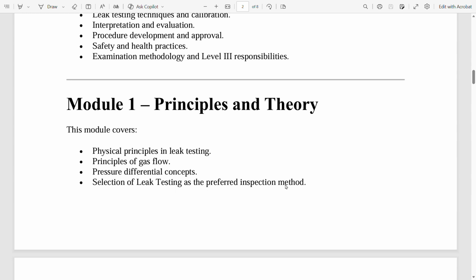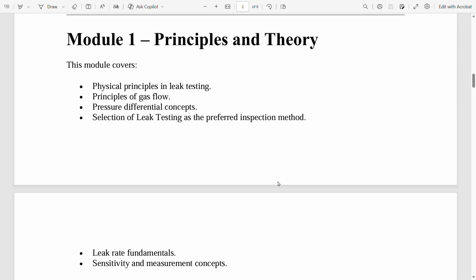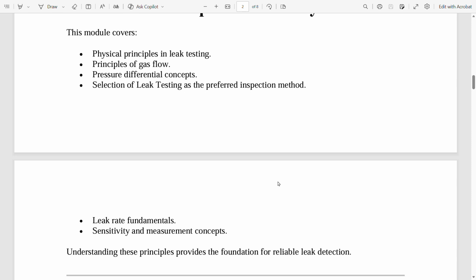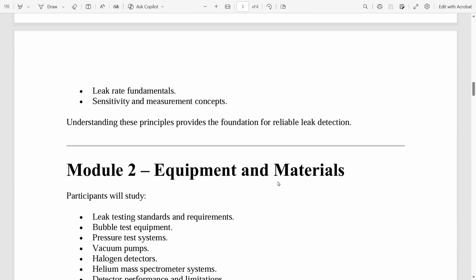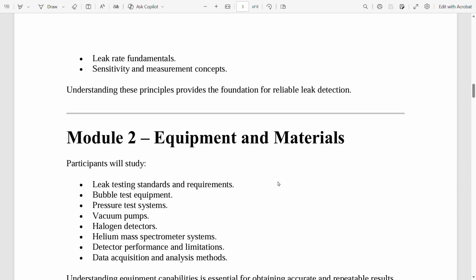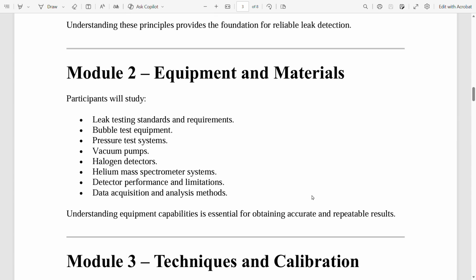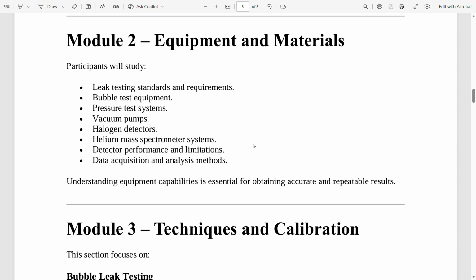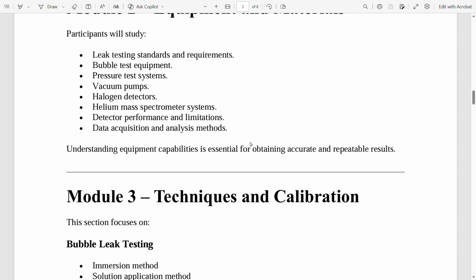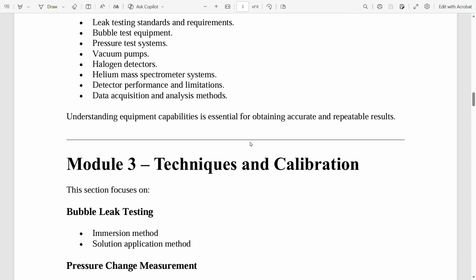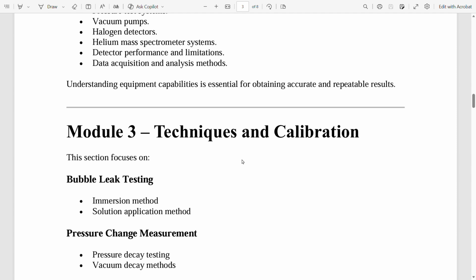Module 1: Principles and Theory. This module covers physical principles in leak testing, principles of gas flow, pressure differential concepts, selection of leak testing as the preferred inspection method, leak rate fundamentals, sensitivity and measurement concepts. Understanding these principles provides the foundation for reliable leak detection. Module 2: Equipment and Materials. Participants will study leak testing standards and requirements, bubble test equipment, pressure test systems, vacuum pumps, halogen detectors, helium mass spectrometer systems, detector performance and limitations, data collection and analysis methods. Understanding equipment capabilities is essential for obtaining accurate and repeatable results.